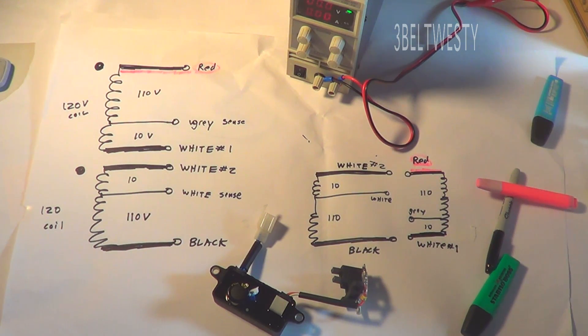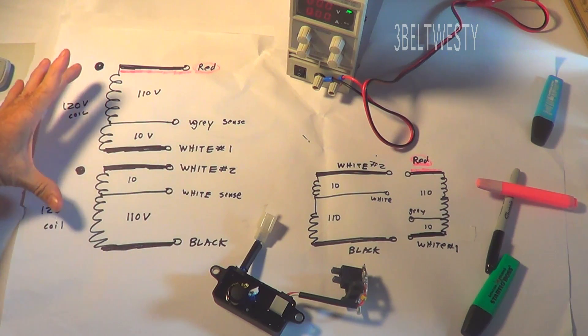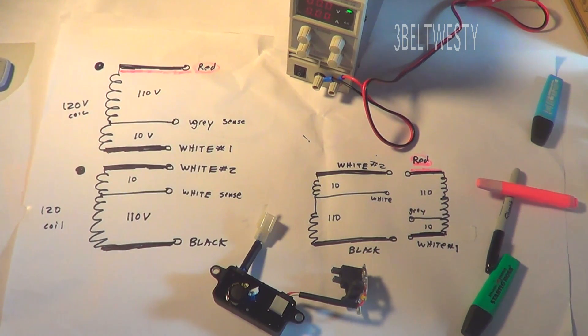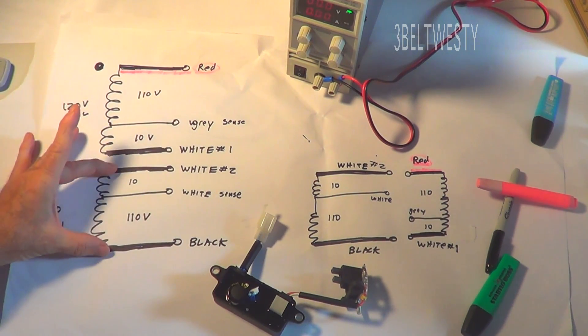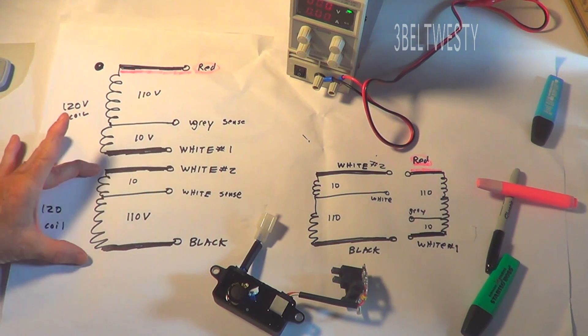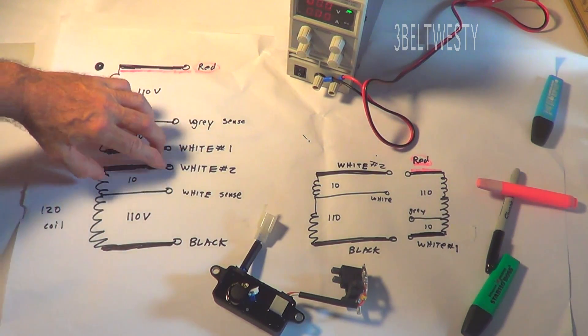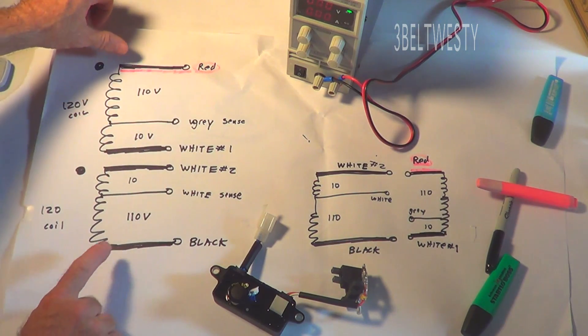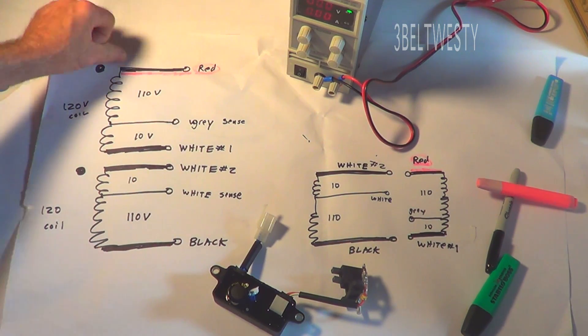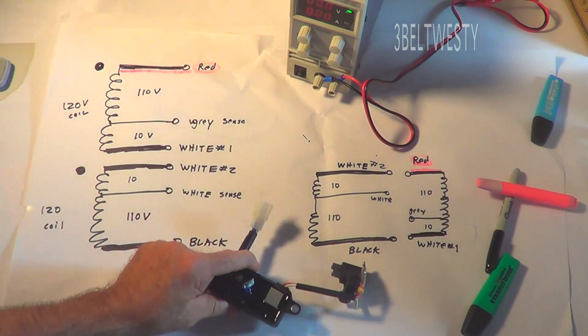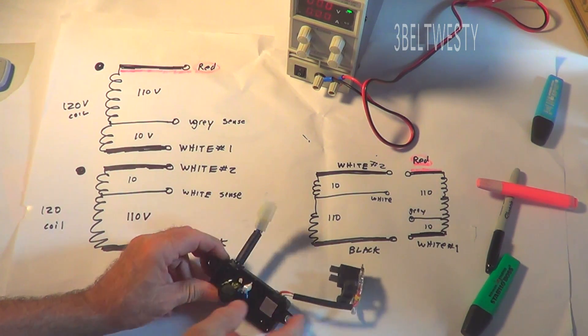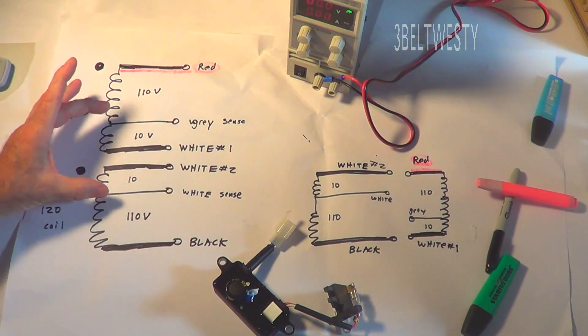Okay, this is for the Harbor Freight 3200 watt generator stock condition. You've got 230 volts output across here. Here's the 110 volt coil, 120 volt coil, here's the other 120 volt coil. They connect the two whites together, got 240 volts across that.